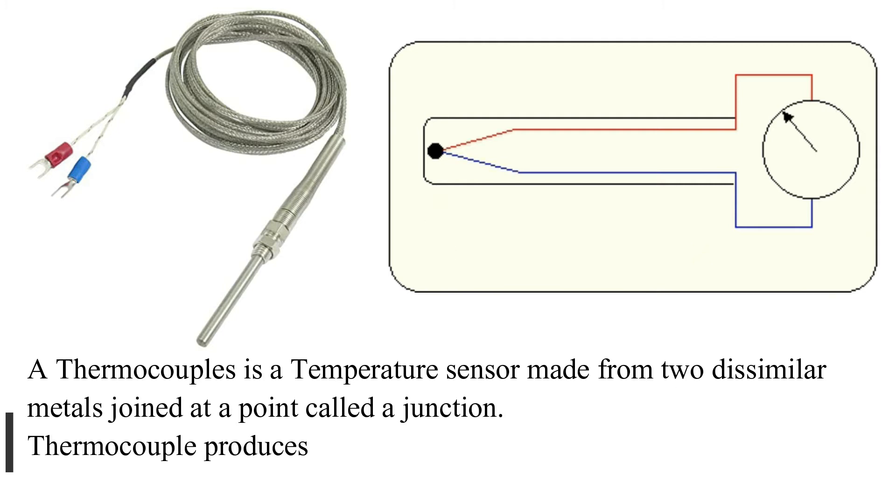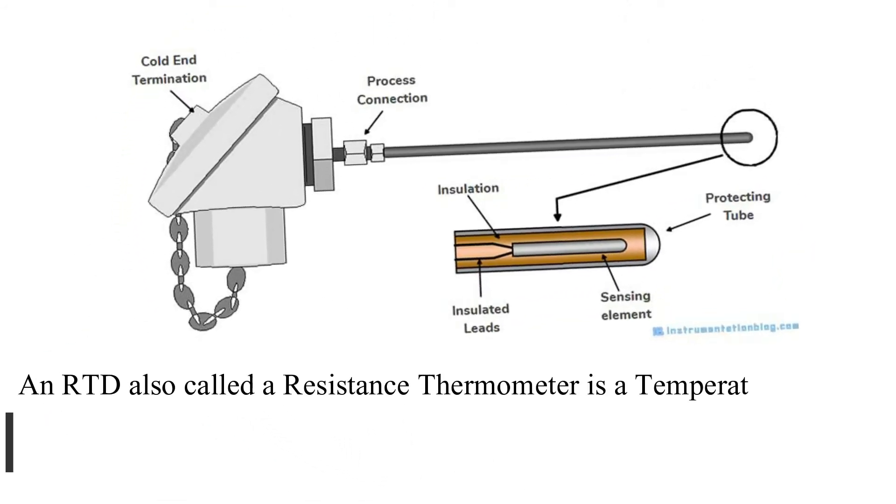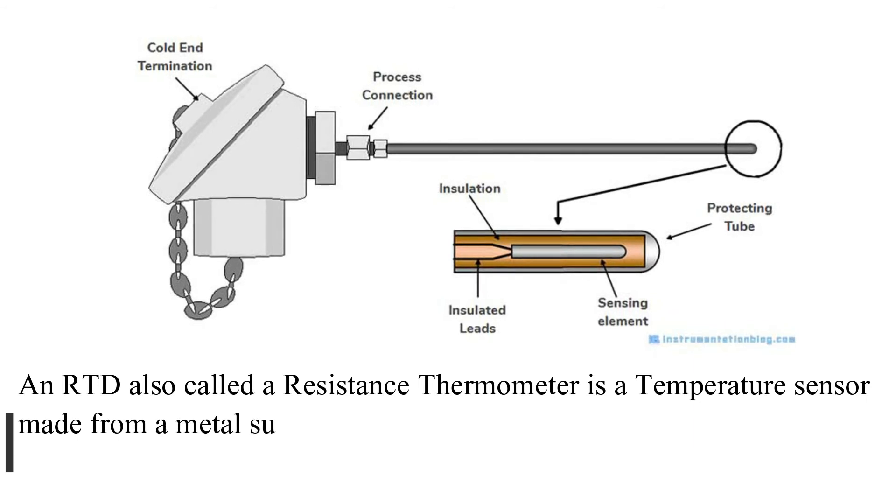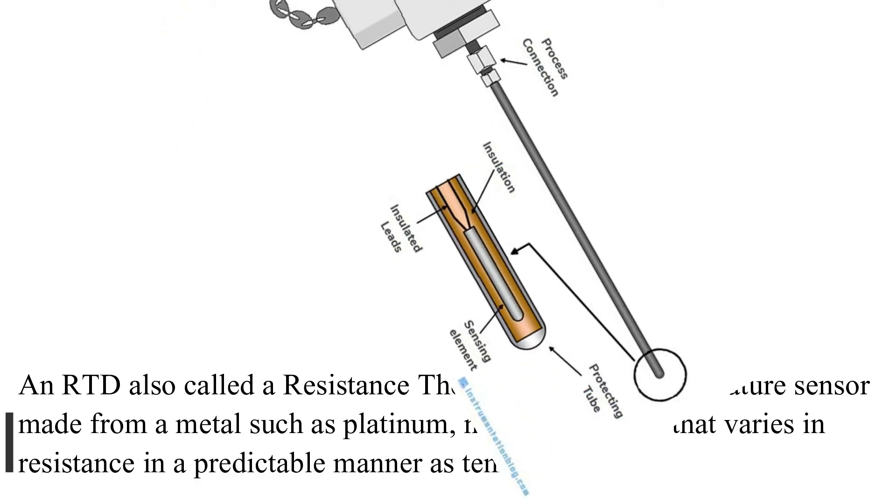Thermocouple produces a small voltage that is temperature dependent. An RTD, also called a resistance thermometer, is a temperature sensor made from a metal such as platinum, nickel, or copper that varies in resistance in a predictable manner as temperature varies.